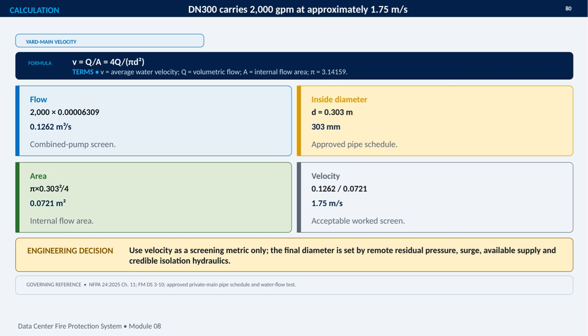The important engineering point is that this velocity is a screening metric, not the final basis for selecting the pipe diameter. The final decision must also consider remote residual pressure, surge, available water supply, and credible isolation hydraulics. The governing checks reference NFPA 24, Chapter 11, FM Data Sheet 3-10, the approved private main pipe schedule, and the water flow test. So, this calculation is a useful verification screen, but not a substitute for the complete hydraulic assessment.